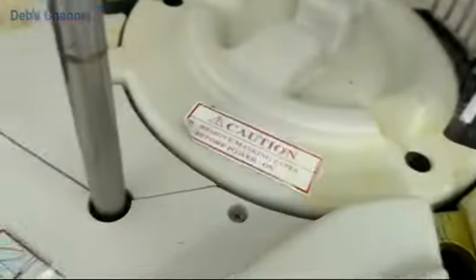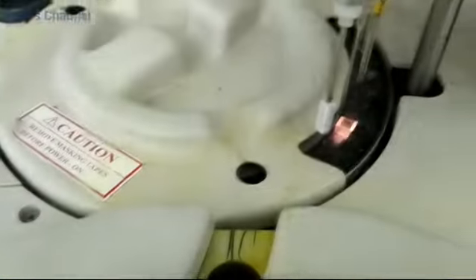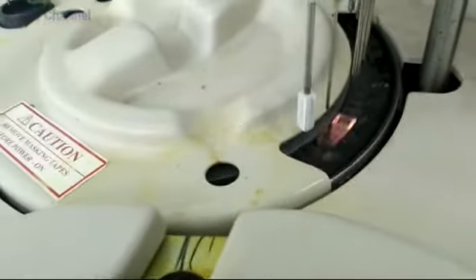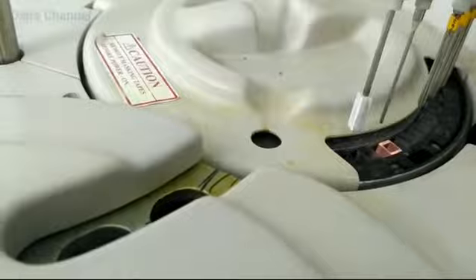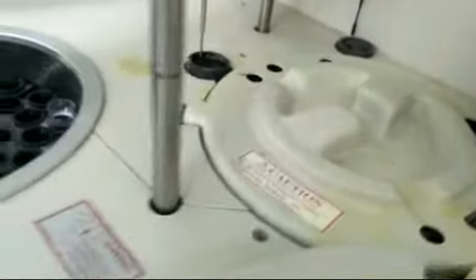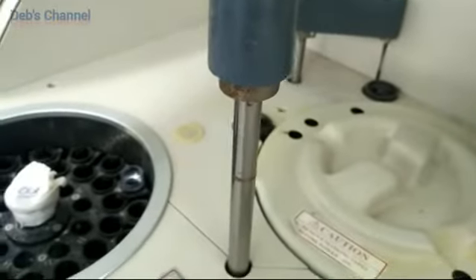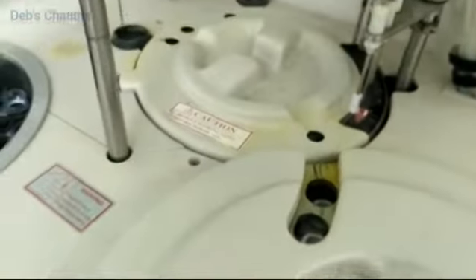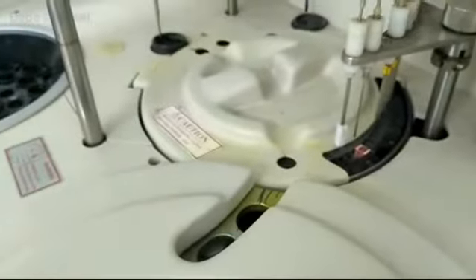In the reagent tray, you can see that the reagent is scanning gradually for detecting the position for the required reagent of the selected test. We selected sugar, urea and creatinine. So the machine will detect the reagent position, and this is the cuvette. In this machine, the hard glass reusable cuvette is used, and the probe. Now see, the probe is taking the reagent. To start the test, at first the probe is taking reagent from the appropriate reagent position.